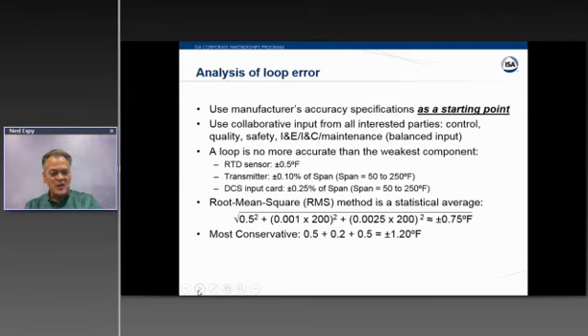And some people don't like the RMS method. So for those of you out there that don't like doing an average, or maybe you think it's a game to use statistics, you could simply add the errors together. So if each component had drifted to the max in the same direction, this loop would be off by a potential 1.2 degrees. So maybe you'd set your tolerance to 1.5 degrees or even 2 degrees. So that gives you just some ideas that you need to consider: the loop is only as accurate as the weakest element making the measurement.